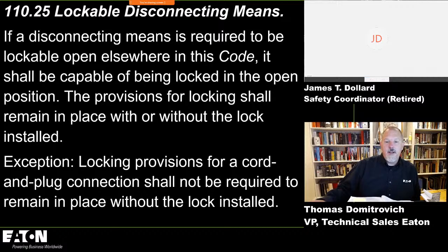So from a National Electrical Code perspective, we put a lot of requirements in that speak to providing lockable disconnects for different types of loads, so that the electrical worker can turn off power while doing de-energized work. In this case, 110.25 talks about it: if a disconnecting means is required to be lockable open elsewhere in the code, it shall be capable of being locked in the open position.